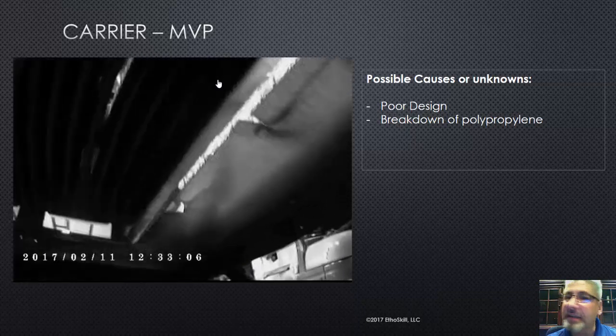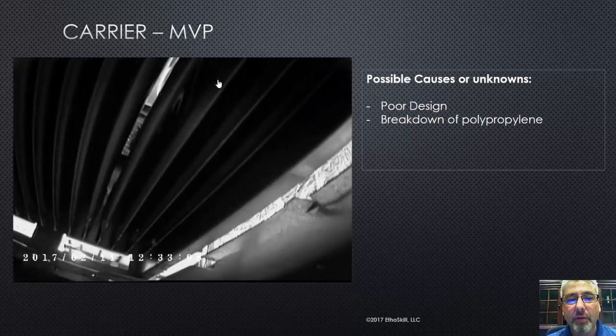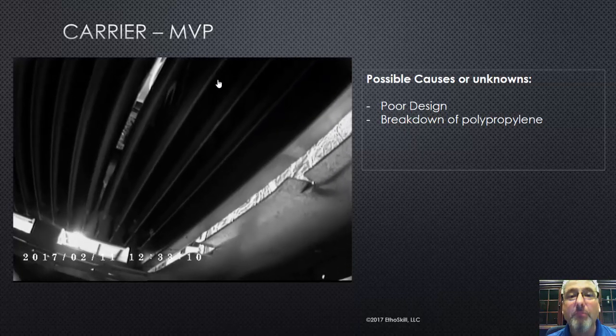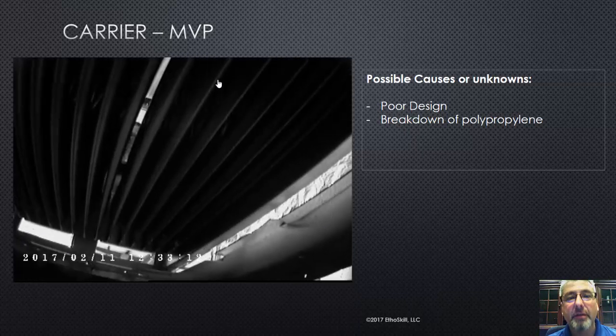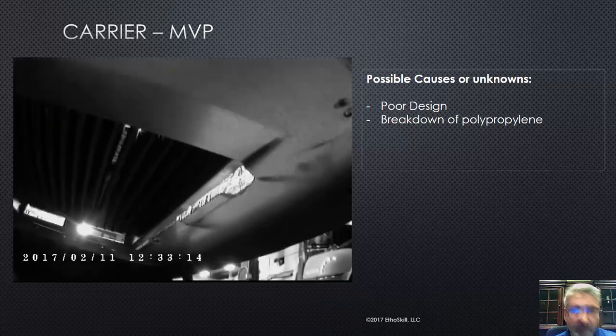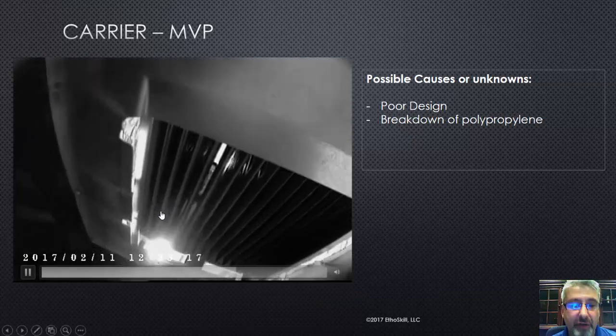However, that condensate is acidic, and that condensate will destroy metal. That's why most secondaries built today are made out of stainless steel. This one was an aluminized steel with a polypropylene coating.